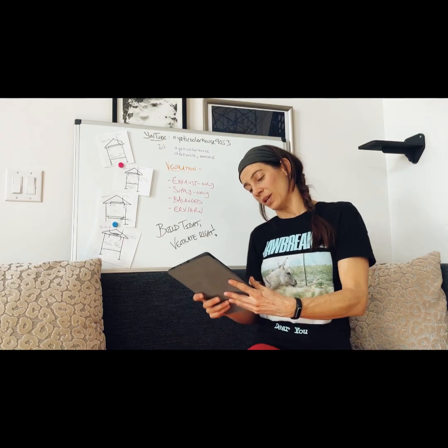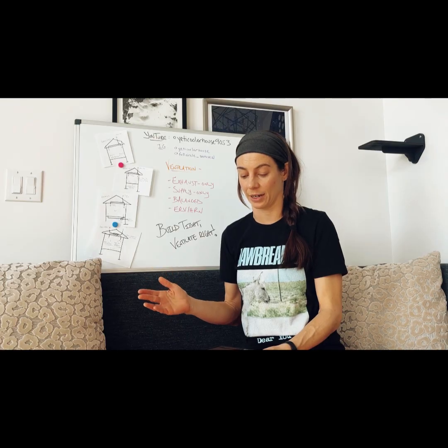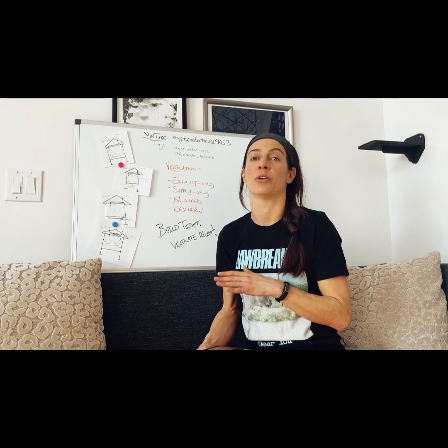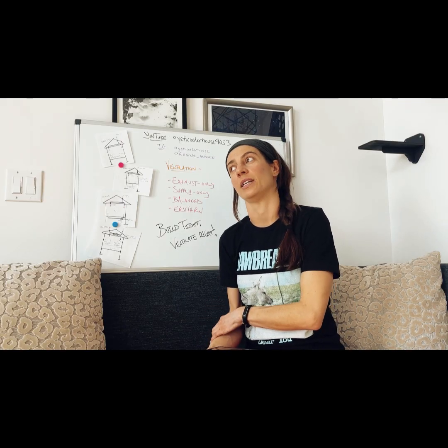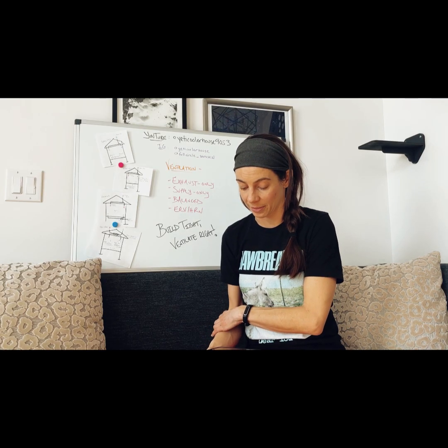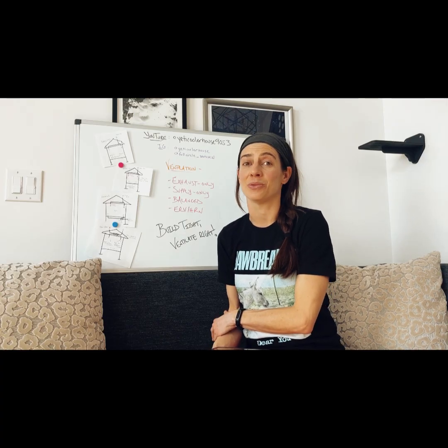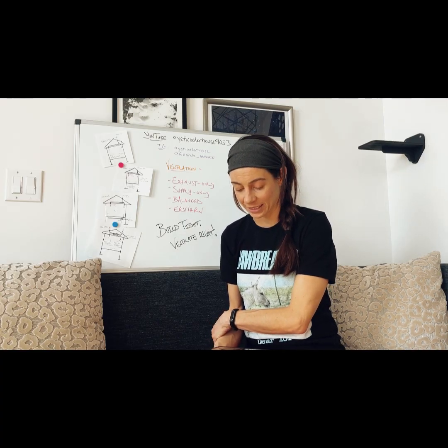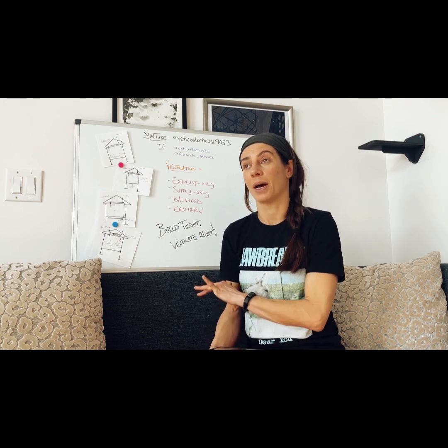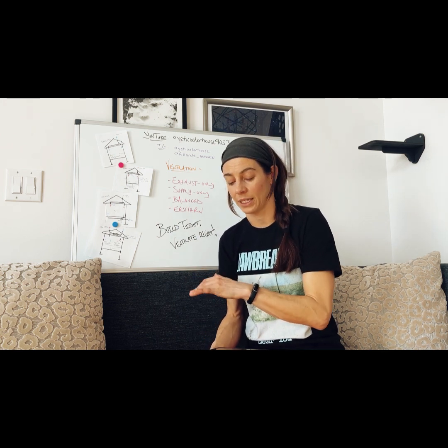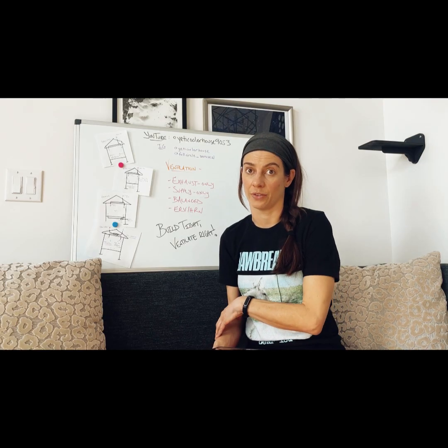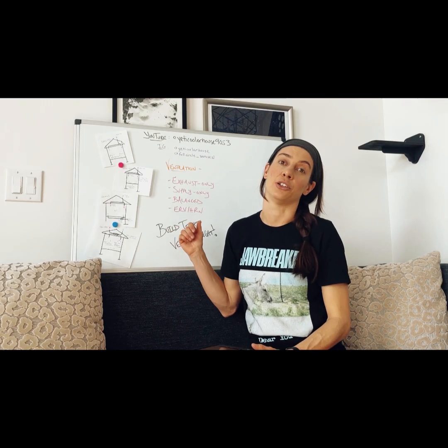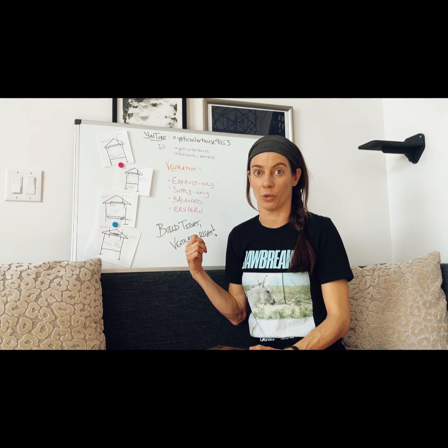So to conclude, fresh air is necessary, and it's best to control, filter, and disperse this air instead of relying on natural ventilation. Supply only is more common in warmer climates. Exhaust only is more common in colder climates, but should definitely not be used with any open combustion appliances. Balanced ventilation can be achieved by combining supply only and exhaust only, or you can use the ERV or HRV. An ERV handles the latent load or humidity, and you want that in your drier climates. HRV, good for more humid climates.